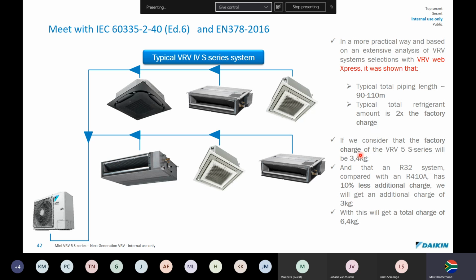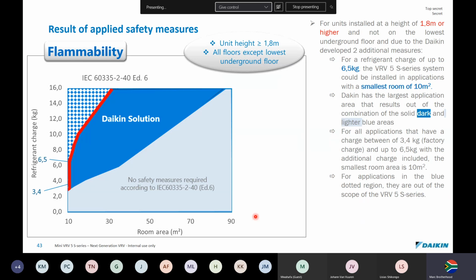That sounds a bit confusing, but what they pretty much mean is that most countries are using double the charge on a 410 system, and if you take 10% and subtract 3.4, you'll get 3 kilos. So what they've worked out is that on a typical R32 design, you're going to get a total charge of 6.4 kilograms on the system.